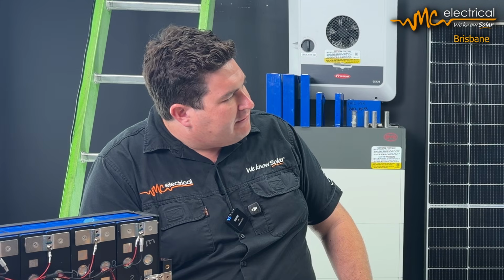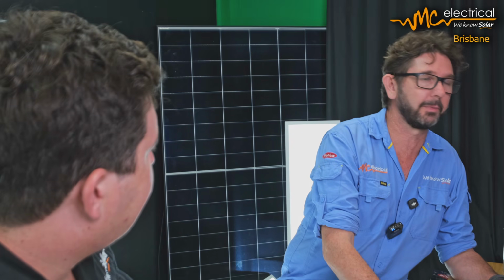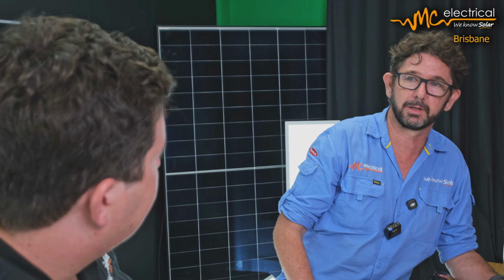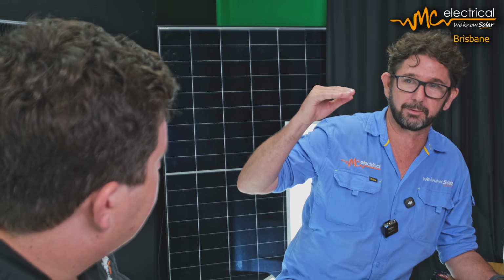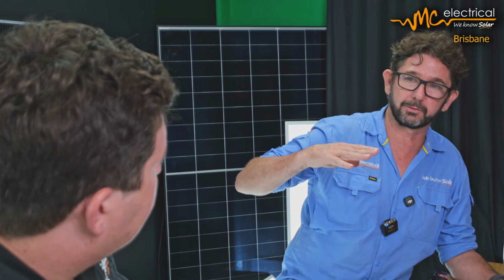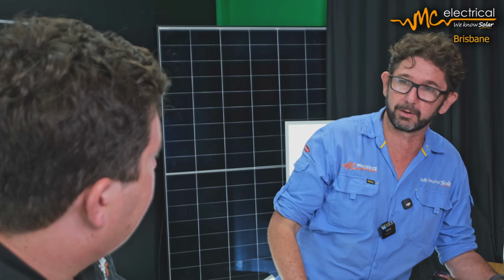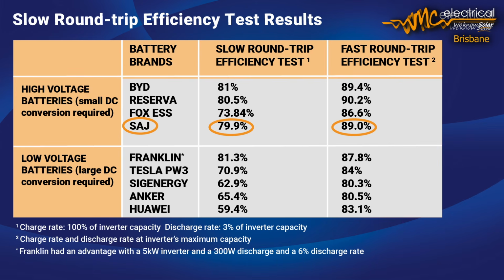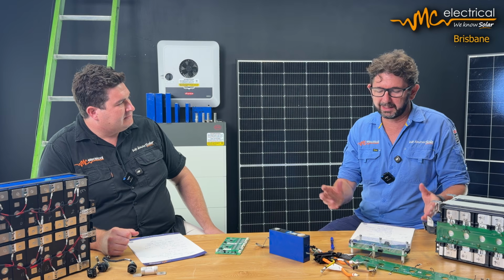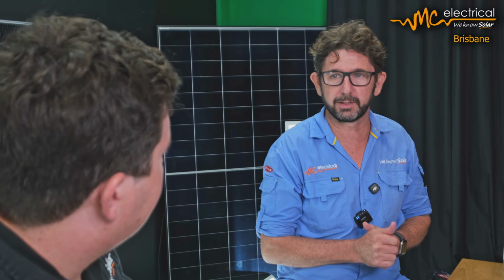So these batteries must be very efficient, Mark. You've been doing some round trip efficiency testing on a range of products, and I think we've just finished it with SAJ too. It does, and no surprises at all — it's pure physics, mate. We got the same as any other high voltage battery: sort of 90% on the fast round trip efficiency test and 80% on the slow round trip efficiency test. No surprises there at all. Let's put the numbers up on the screen, but I think it actually did a little bit better than Fox. To be fair, we're not nitpicking over the small differences. This isn't lab condition testing, but it is proving that within range, all these high voltage batteries are pretty well similar.